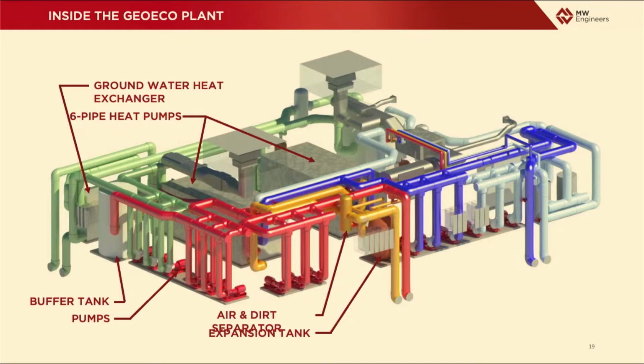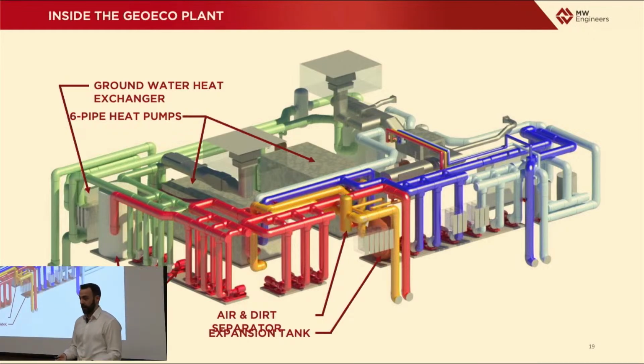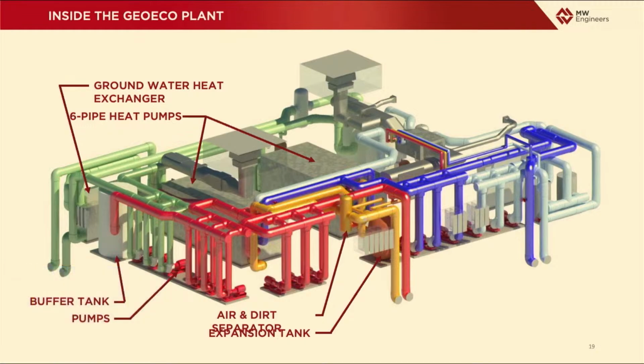And then the green pipes are the groundwater pipe. So that's what's actually interfacing with the aquifer. Some other really important pieces of equipment here, you can see in the back corner is a groundwater heat exchanger. So something to note about this geothermal system is it's using the groundwater, or the aquifer water, and it comes into this building. It's not used, it's not consumed. So it comes into the building and then it's re-injected. There is no consumption of this water. The groundwater is only an energy exchange, so we trade energy with it.